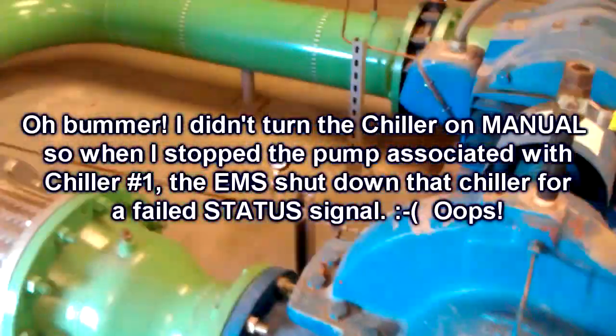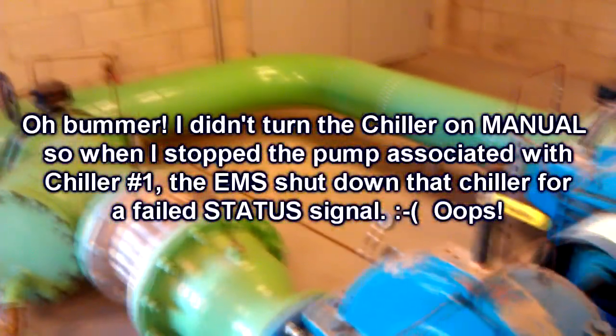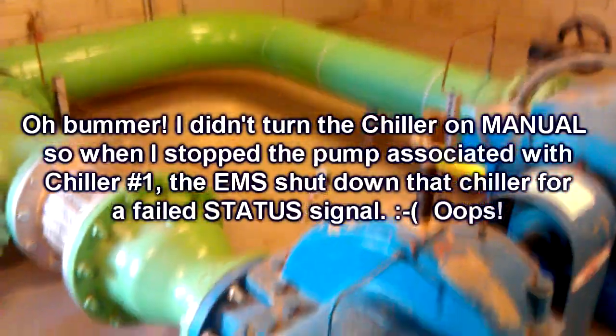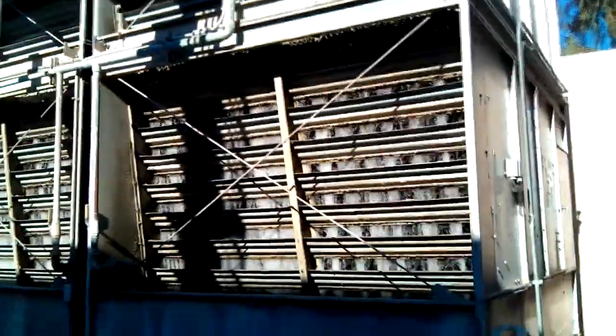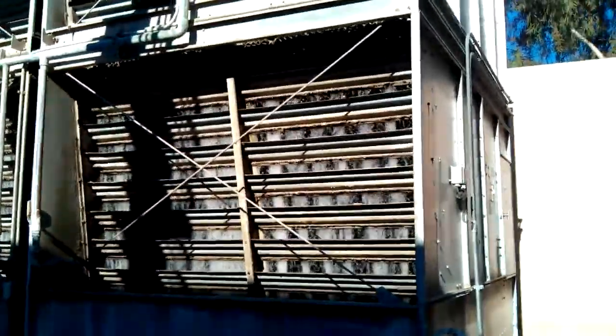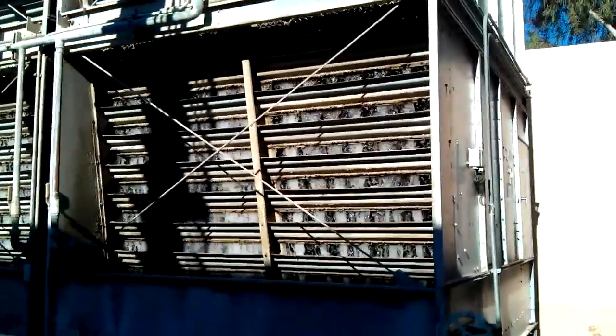Oh shoot, I forgot to turn the chiller on manual. It's going. And it's actually flowing nicely, which hasn't been flowing like this for a while. Got the second pump running, going through chiller number 1, redirected, but I forgot to flip the manual switch on, and the chiller shut down when the EMS saw that I turned off the pump. So I failed to keep the chiller running. Got to go turn that back on. Luckily that's a VFD one and doesn't cost a fortune to start up.